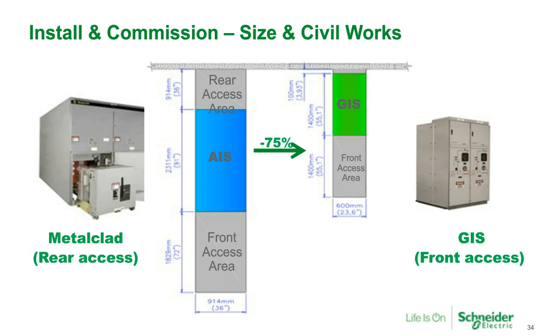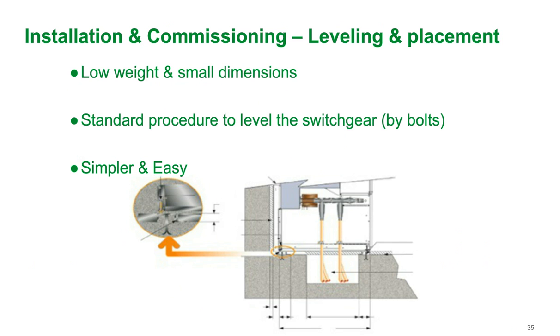As we all know, with GIS you have a drastically more compact switchgear. Even at 5 and 15 kV, the footprint is much lower, but at that point you have to think about two-high versus single-high construction. Another consideration with GIS is installation and commissioning. GIS is typically lower in weight and smaller, so you need less of it, and it doesn't require any special supporting from a weight perspective, especially in an E-house or prefabricated building.